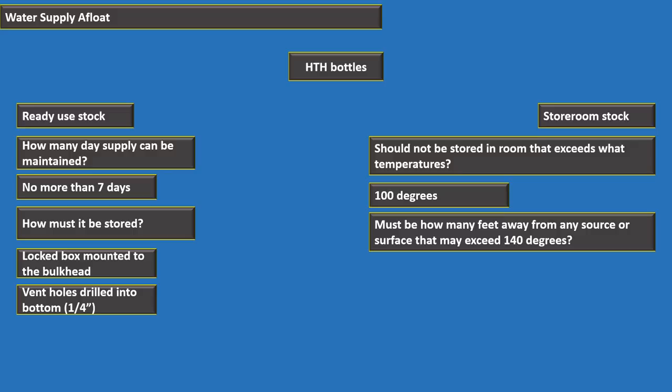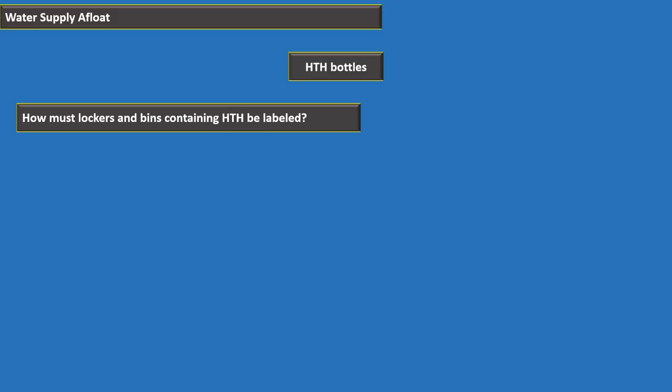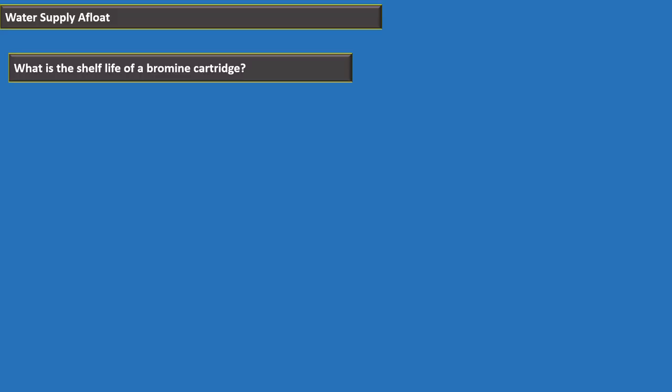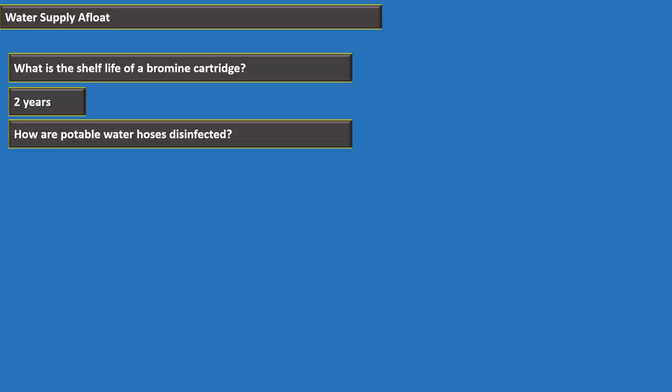Lockers and bins containing HTH must be labeled with red letters on a white background stating 'HAZARDOUS MATERIAL — CALCIUM HYPOCHLORITE.' The shelf life of a bromine cartridge is two years. Potable water hoses are disinfected with 100 parts per million free available chlorine with a two-minute contact time, then flushed with potable water.